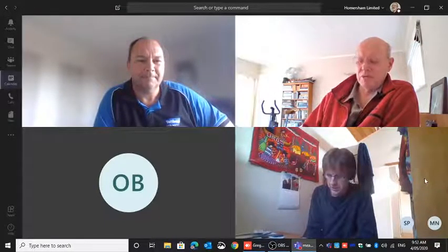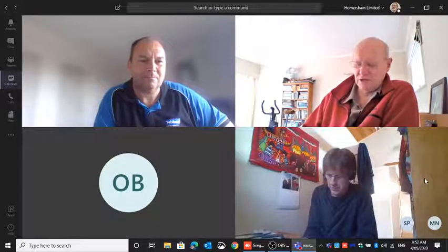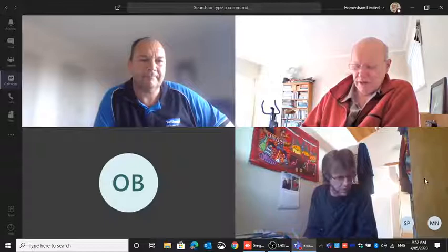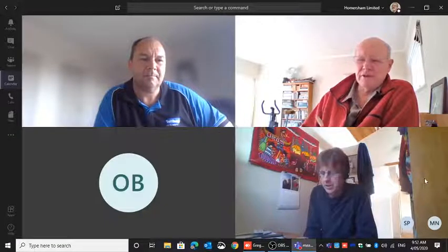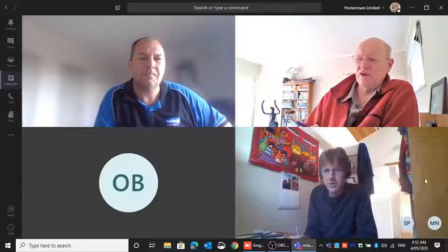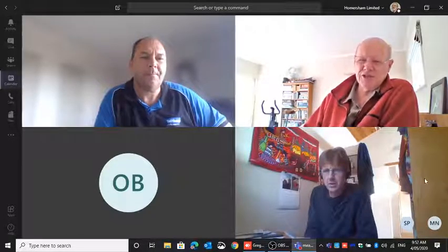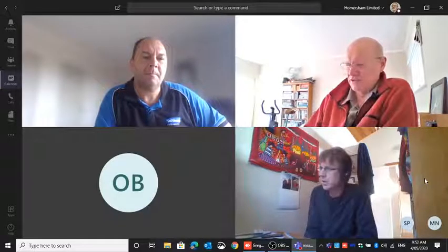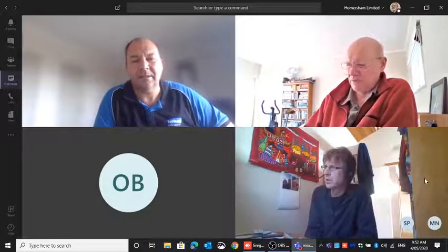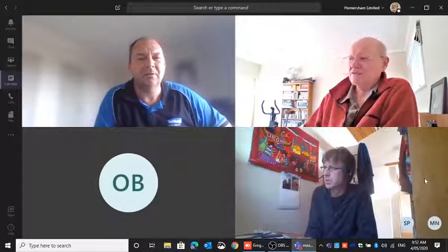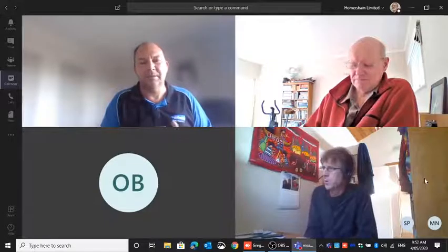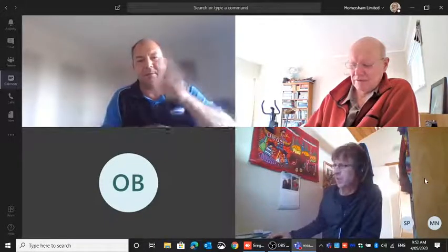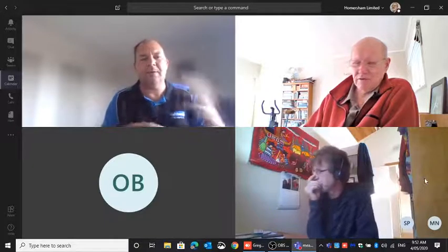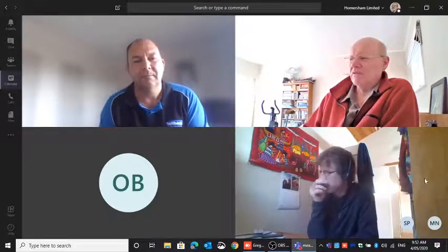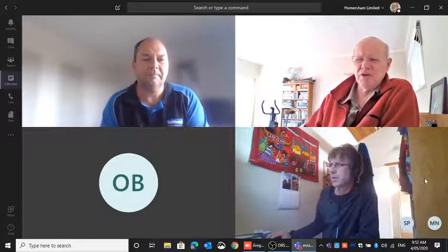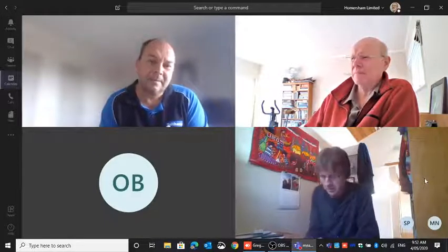So with a portable sensor, if you wanted to use it in a fixed installation, e.g. the clarifier at Waimate West, I gather there's no IO, so you'd have to rely on the instrument vibration and a detector to pick that up to send it off to your SCADA system. Is that the way I would...? Well, like I said, the portable unit is a data logger, so I wouldn't use that for continuous measurement. You go on site, you do a measurement, and you will see where your fluff level is. You come back every 2 or 3 hours and you do a measurement. You probably use your eye for that, but anyway.